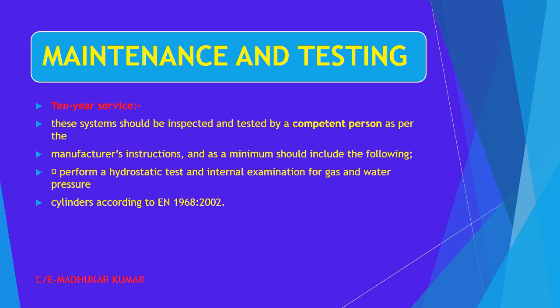10-yearly, these systems should be inspected and tested by a competent person as per the manufacturer's instructions, including annual, including 5-yearly, everything. And as a minimum should be included, perform the hydrostatic test and the internal examination of gas and water pressure cylinders. Okay, so the vessels which are there, which are being pressurized, hydrostatic pressure testing must be done on a 10 yearly basis, and the requirement, if you are going for that, then it is EN 1968-2002. That is the requirement for hydraulic testing of gas and water pressure cylinders.